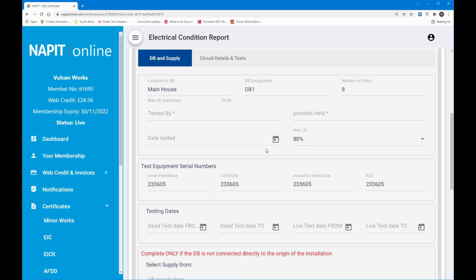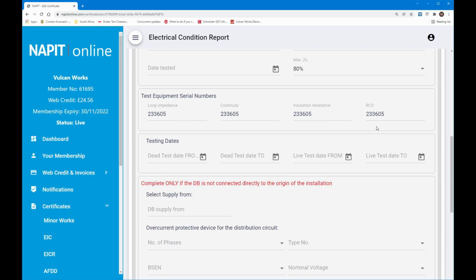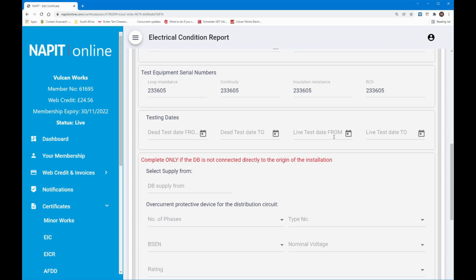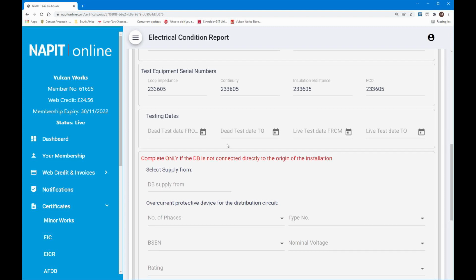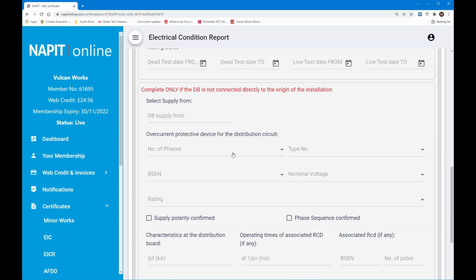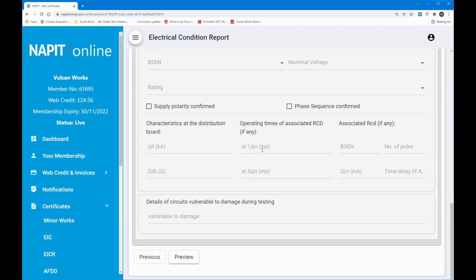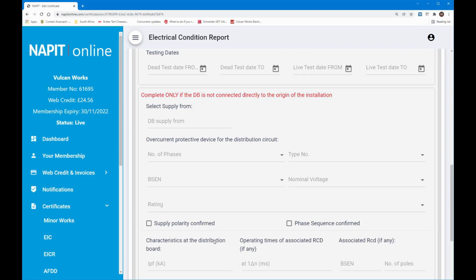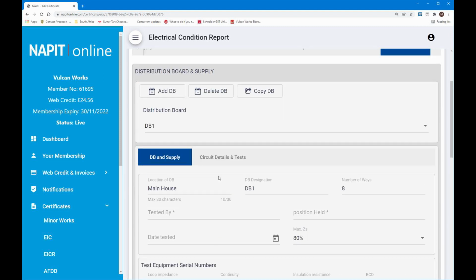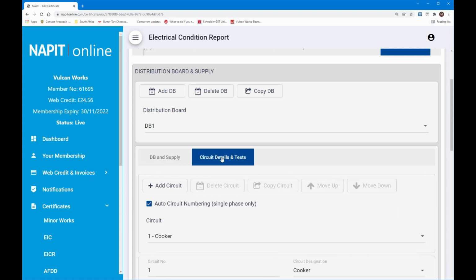Those I would fill in at the end, and we're using the values from the on-site guide for Zs. That's the tester that was used, and I will fill in the testing dates later on. Now I don't need to fill in this bit this time round because I'm dealing with a DB that is connected directly to the supply. This will be filled in when we do the conservatory one in a second. So that's the first DB. So best thing to do is go on to the circuit tests. I've pre-filled in some of this stuff except for the test results.